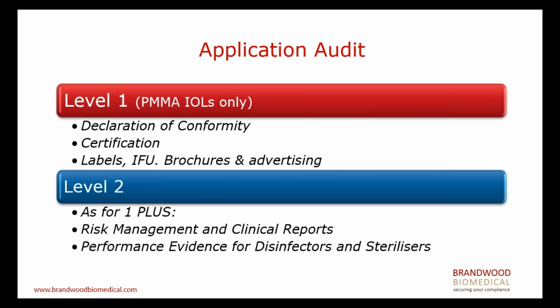So what's involved in the audit? There are two levels of audits. When I refer to the mandatory application, I'm referring to the level 2 audit there. But level 1 is things like review of the declaration of conformity, making sure your CE certificate or your conformity assessment certificate is valid, and also reviewing your labels, your IFU, brochures, advertising, making sure sponsor labels are correctly placed on the device, and things like that.